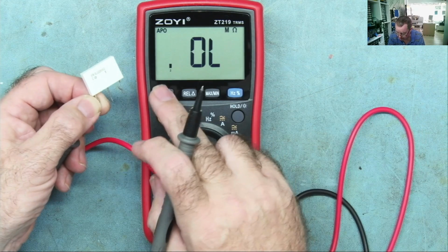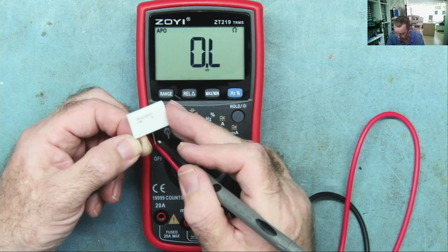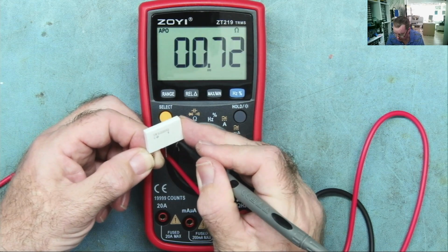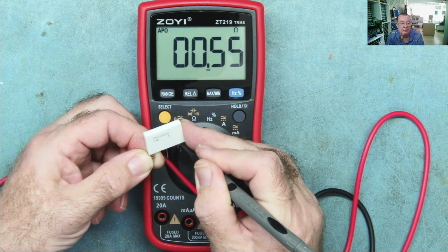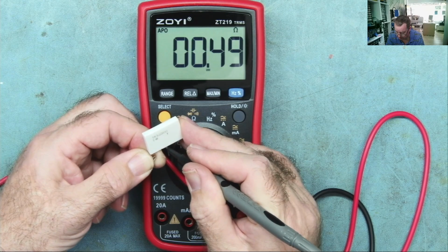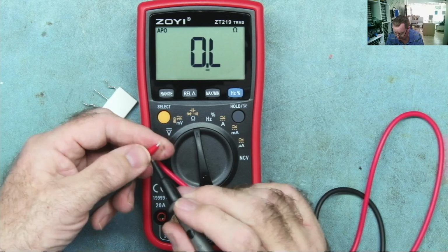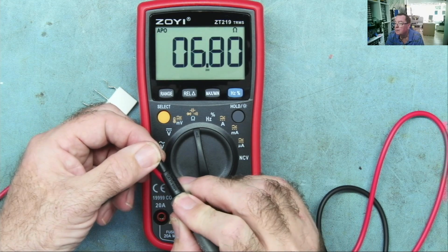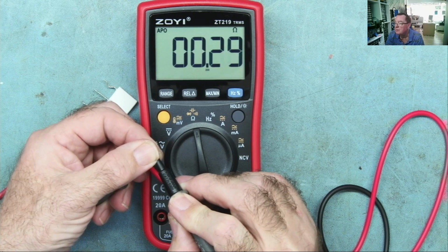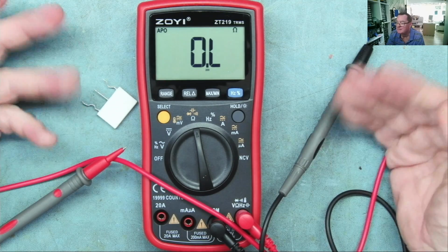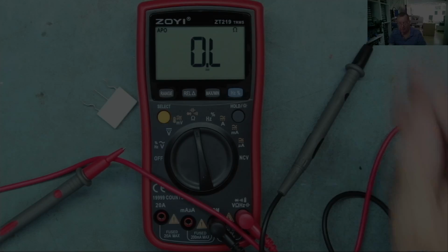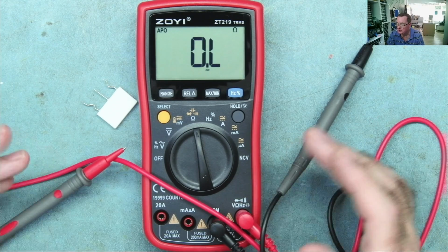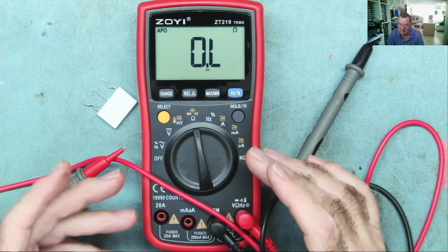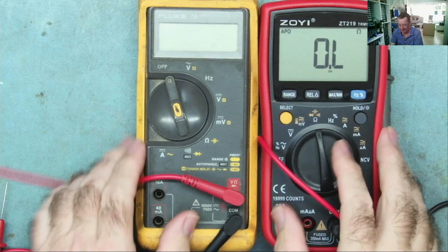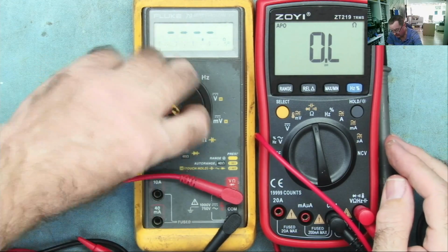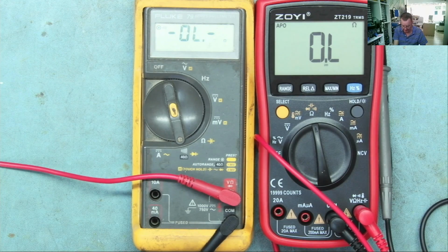Let's go to manual. I want to go to ohms range, see if it does it a little bit better. So 0.5 across the whole thing, 0.4 across there. So this probably isn't zeroed. It's quite close. Okay. I haven't checked in the manual to see if this has a calibration mode. Let's have a look. Yeah, I've had a quick look. I can't see any way to actually calibrate this. I will say it's reading that quite well though. My Fluke, which is a very similar size by the way, on low ohms range, and this does have a calibrate function.